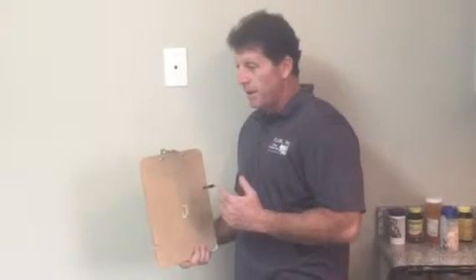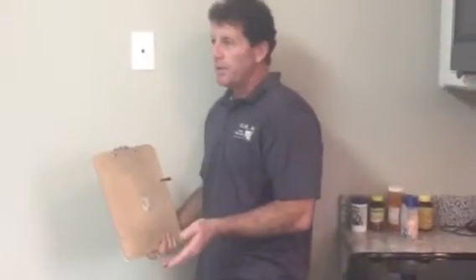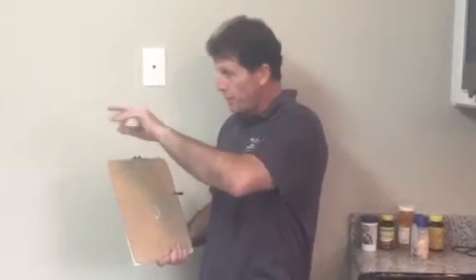Everything that I said is based on what was visible and accessible to me. I don't have any real major concerns. And the final piece of the puzzle is really the electrical. It's Square D equipment. No insurance company I know of has a problem with that type of equipment. The wiring that was visible and accessible to me in the panel and the sample receptacles where I took some covers off is copper. So we don't seem to have any problem with material or brand of electrical panel.